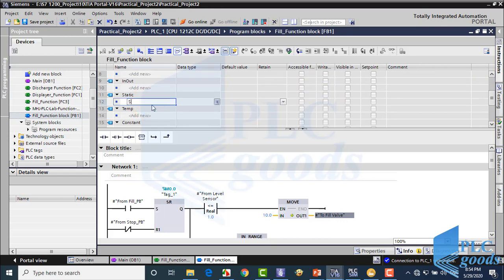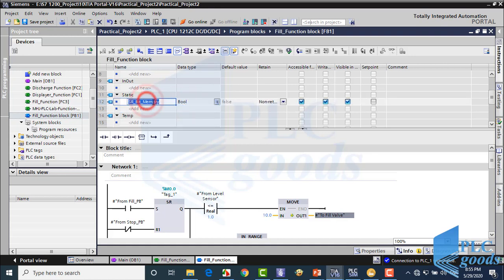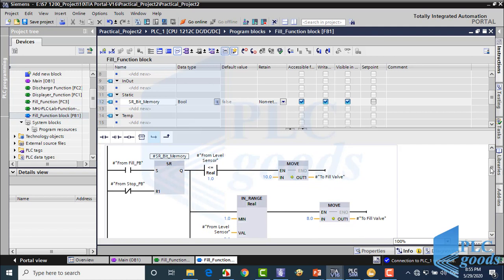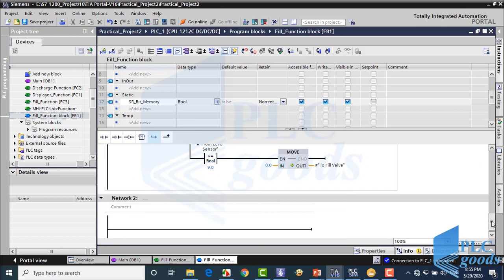Now I can define a bit memory here and use it for the SR instruction. If you test this program you will see it won't work correctly — here is another problem. If the fill valve gets a value of 8 from this line and I press the stop push button, the fill valve holds its last value and stays on. To solve this problem, I use the stop push button to move 0 to the fill valve.